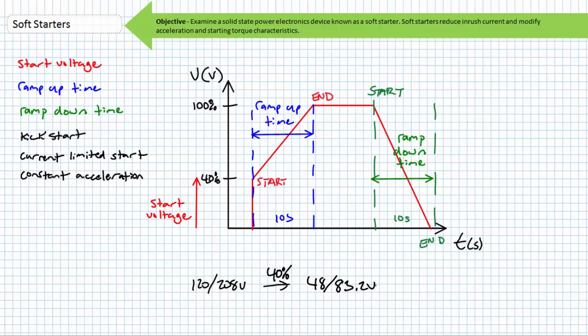Advanced soft starters may also offer the ability to kickstart a driven load by allowing a brief initial boost of current at startup to break away loads with a large static inertia. This kickstart provides a current pulse for a selected period of time. The 2 remaining aspects of advanced soft starters, current limited start and constant acceleration, necessitate more involved circuitry in the form of a feedback mechanism.